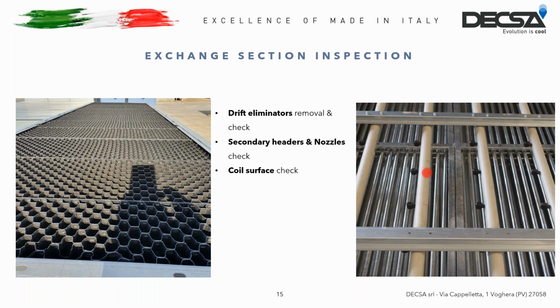As I explained before, it's necessary that the recirculated water sprayed by the nozzles is properly treated to avoid fouling problems on the coil. Consider that a 1 millimeter layer of limestone reduces the performance by 10%, 2 millimeters by 20%, and so on. In this case, you can contact a specialized company to carry out a chemical wash, but in my opinion, prevention is the best way.